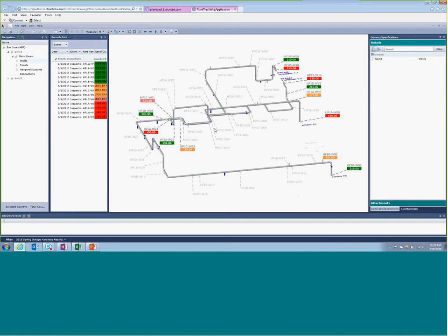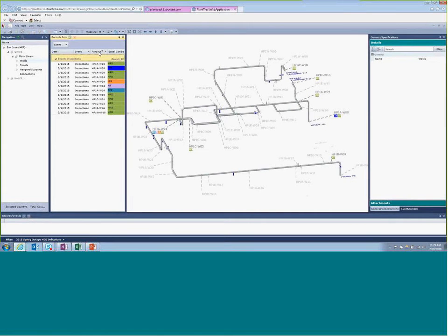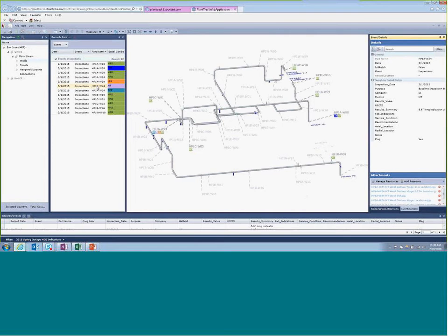So that being said, I want to go back to the NDE indications and focus on these two welds here, weld 24 and weld 8. One of the things that's neat is that I can filter here and basically say, okay, look at weld 8 and then weld 24. So again, coming back to that block that Ulrich mentioned on records and events, this is housing each event for that particular method. So if I look at it and say, okay, weld 24, show me what the mag particle indication found. I have a bunch of attachments here. I'll just show you real quick.